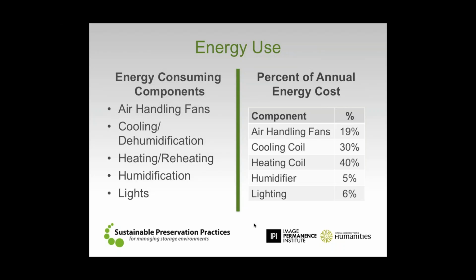Now, in a place like, let's guess, Georgia or Washington, D.C., or even here in Rochester, New York, although Rochester wouldn't be as much of a surprise, oftentimes if you tell folks that the heating coil uses more energy than the cooling coil, it'll cause them to pause for a second and say, well, that doesn't make sense, because it's cooling and dehumidifying that is the most expensive operation. Well, that's true, but if we're dehumidifying via a subcooling reheat process, we talked about that last month also, we realize that we also have to reheat if we are subcooling. That means in many buildings, that heating coil is doing some amount of work all year round, regardless of the season, when the cooling coil really is only doing its job for those months where we need to specifically cool or dehumidify.